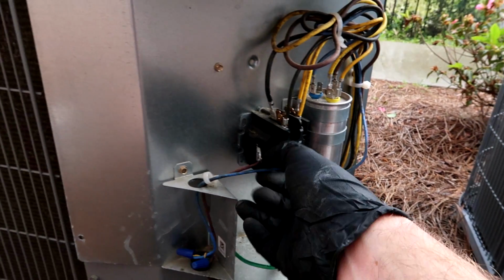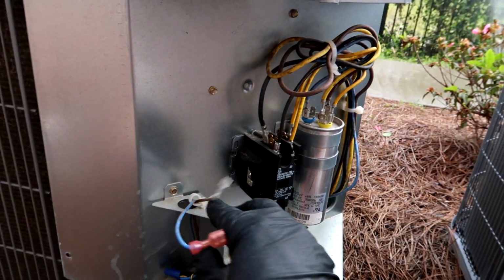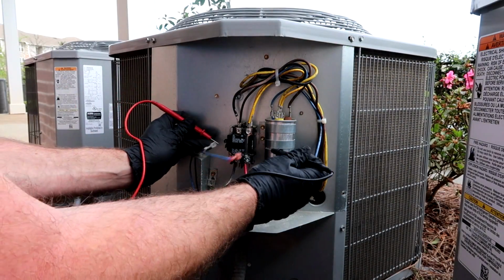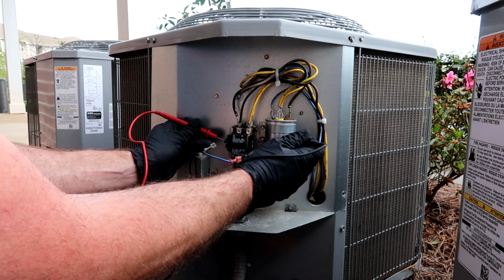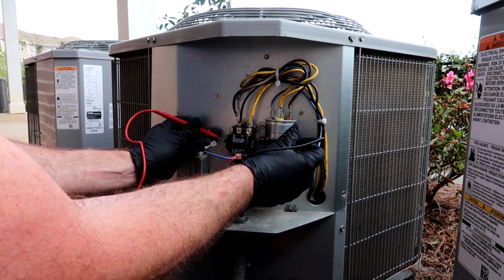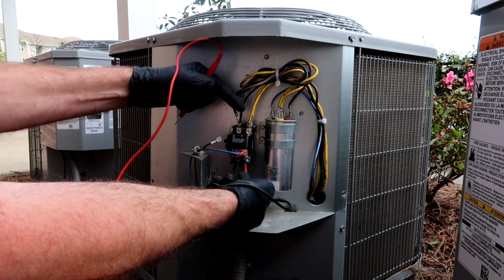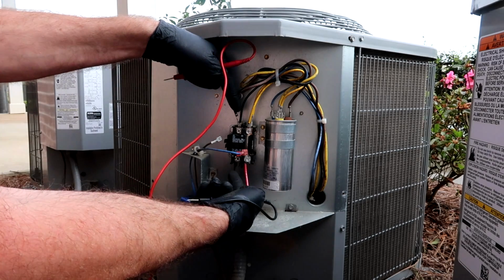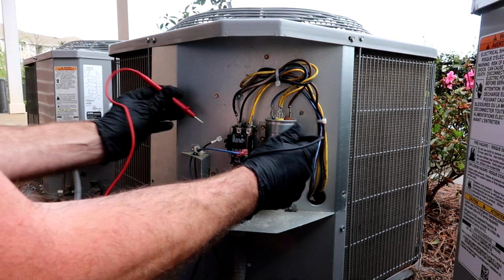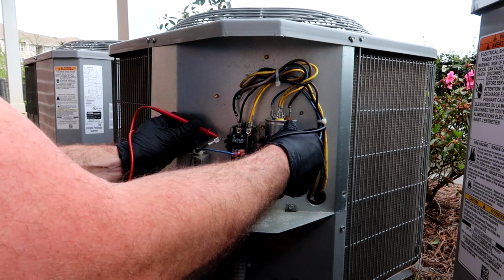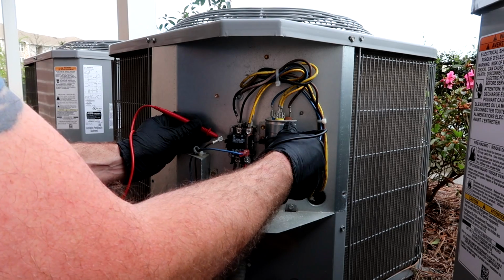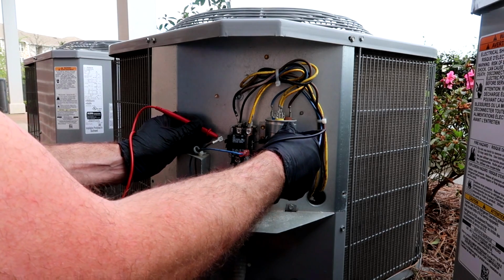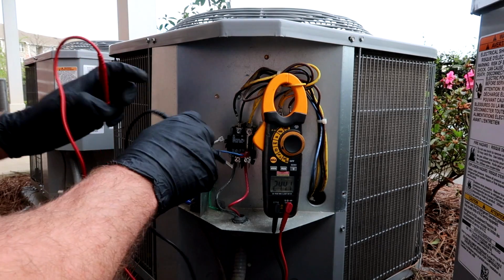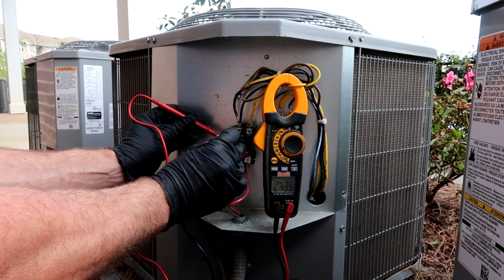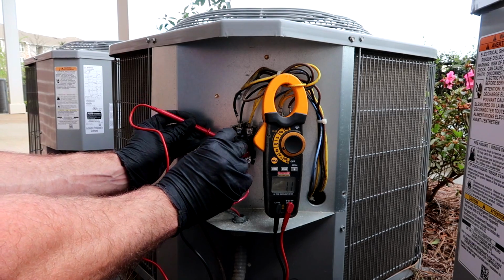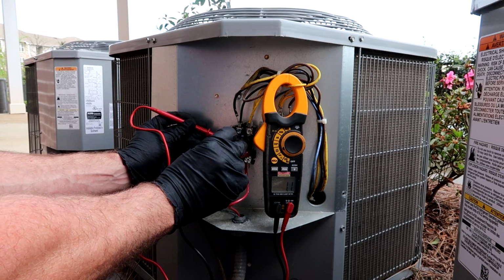Bust out the old contactor here. Alright, one lead on one side of the contactor and one lead on the other for you new cats. The sides are the low voltage and the top and bottom are the high voltage. So this is 120 or 240 and the sides are low voltage, 24 volts. So I'm touching both sides and 1.13. That's a bad contactor. I don't know if you'll be able to see that number, but we'll give it a shot. Touching both sides of the contactor. 1.1. So that is a bad contactor.